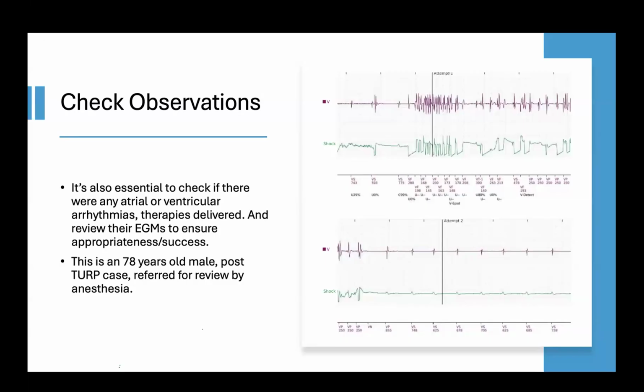And then when we interrogated the device, it appeared that the cautery actually affected the device function, and it did show some noise. That noise did trigger the VF mode of the device, and then the device recognized this as a VF and started a ventricular pacing therapy while it was charging to deliver the shock, but eventually it was diverted as the cautery stopped.